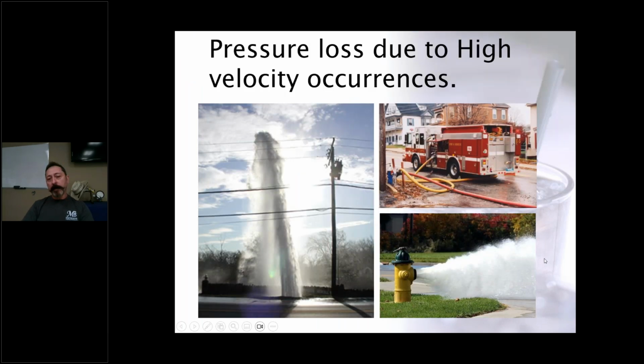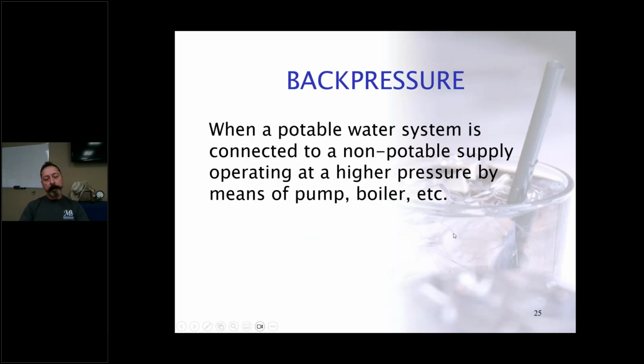So the situations that cause back siphoning to occur are firefighting situations, where they're fighting a structure fire. That'll drop the pressure in our system, creating backflow events. Water main breaks, hydrant flushing, those types of incidents can also occur. So that's back siphoning. The other type of backflow incident that can occur is something called backpressure.